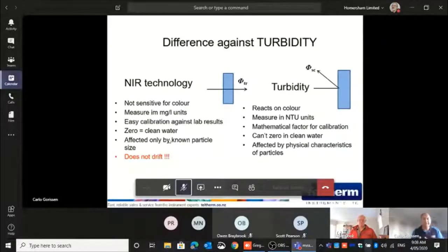Yeah. The big thing is that we measure through absorption of the light, transmission, while turbidity measures scattering of light. That's the main difference. The problem with turbidity is, of course, that you measure in NTU units, and then you have to put a factor in there, the mathematical factor, to create milligrams per liter. While with near-infrared technology, our output is immediately milligrams per liter. Like I said, easy calibration against a lab result.